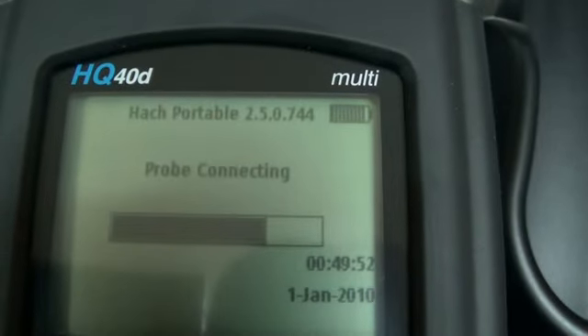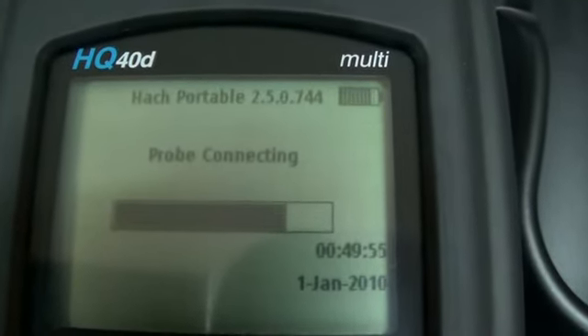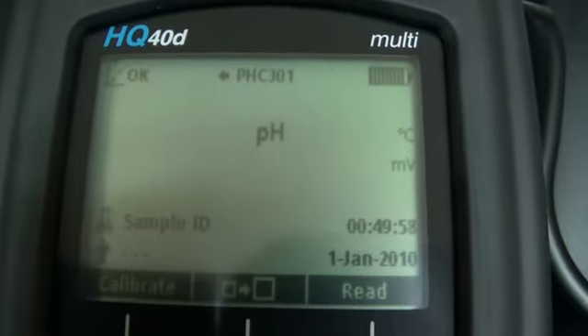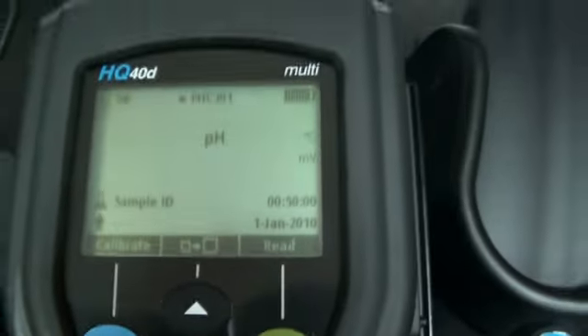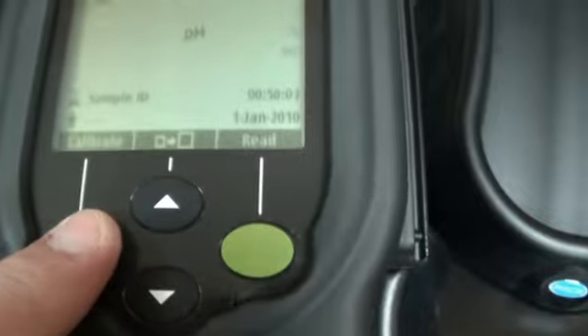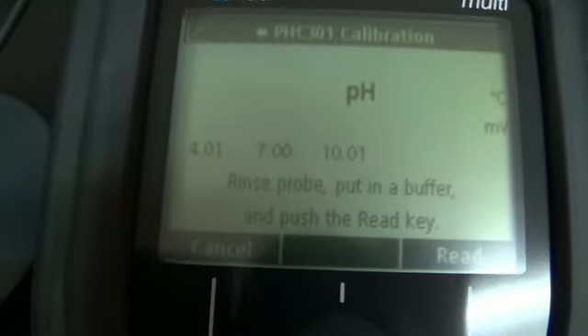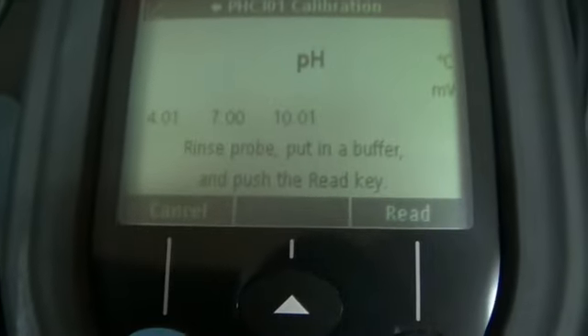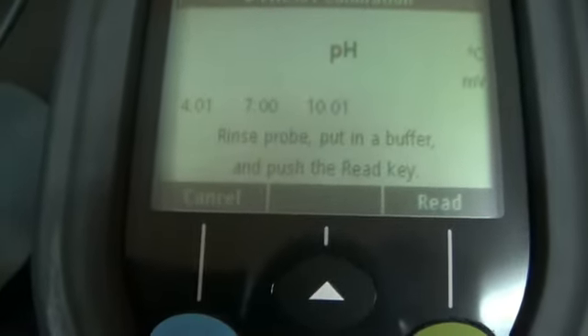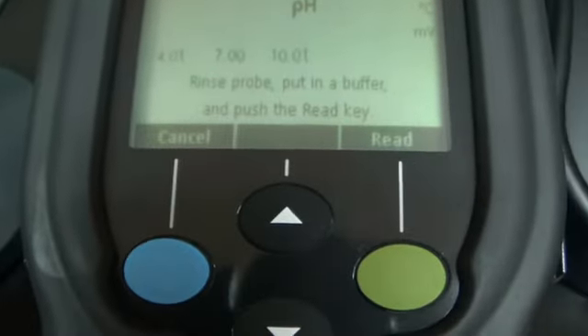You found that it has a probe attached to it, and it knows it's a pH. So we're going to hit calibrate, and right now it knows that it would use a 4, a 7, and a 10 pH. So we're going to rinse the probe and put it in a buffer and press the read key.